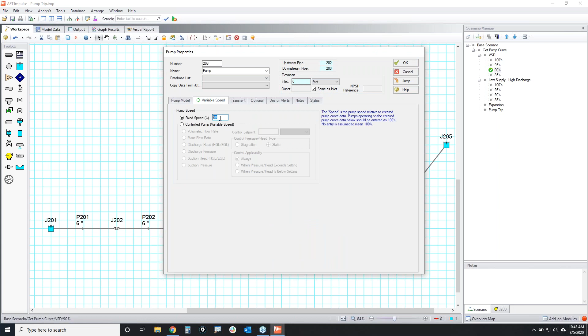So if I open up one of those scenarios, let's do the 90% scenario. I open up my pump and look at that, and my fixed speed is set to 90%. Now, after creating this family of scenarios, I right-clicked on the VSD scenario itself and said clone with children. When I cloned that entire family, it created this family of scenarios, and I simply changed the name to low supply, high discharge.